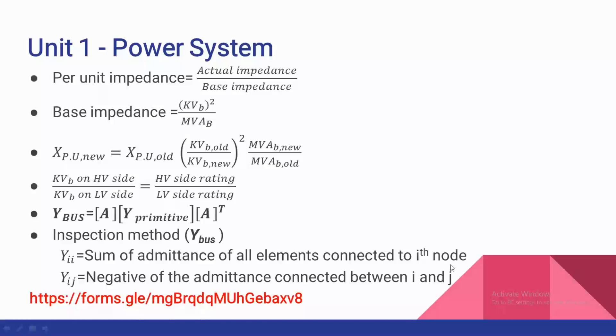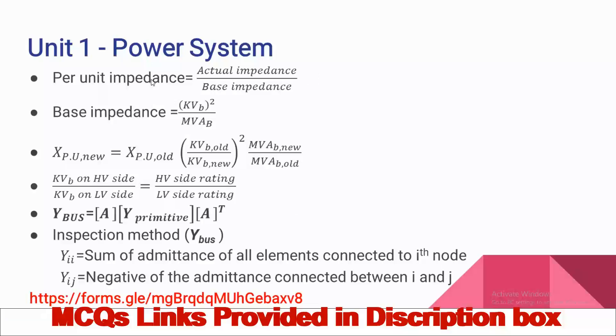Unit One: Introduction. First formula — per unit value. Per unit impedance is equal to actual impedance divided by base impedance. The base impedance formula is kV-base squared divided by MVA-base.